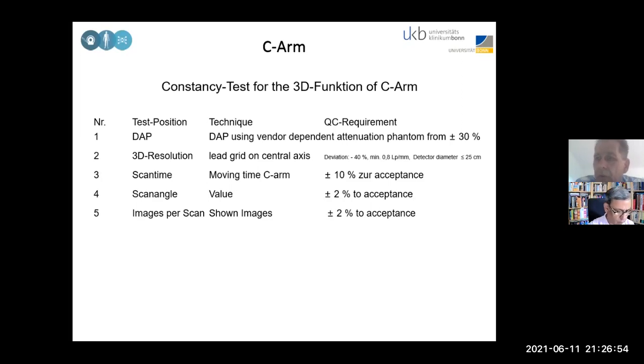Now we come from the mammography. We have a short glimpse on the C-arm, because on Sunday I will give a talk on interventional radiology, on QC on interventional systems. There I will have a more detailed look at the three-dimensional or interventional radiography. I only would like to say that for the C-arms, you definitely have to check other things than in mammography. You have to look more at the dose area product, and then you should see what phantom is actually accepted by the vendor, because some phantoms do not match with the vendor's setups. Then you should check whether he is delivering one or you have to buy one. But the important part is on the right-hand side. You see that there is an acceptance level and a tolerance level.